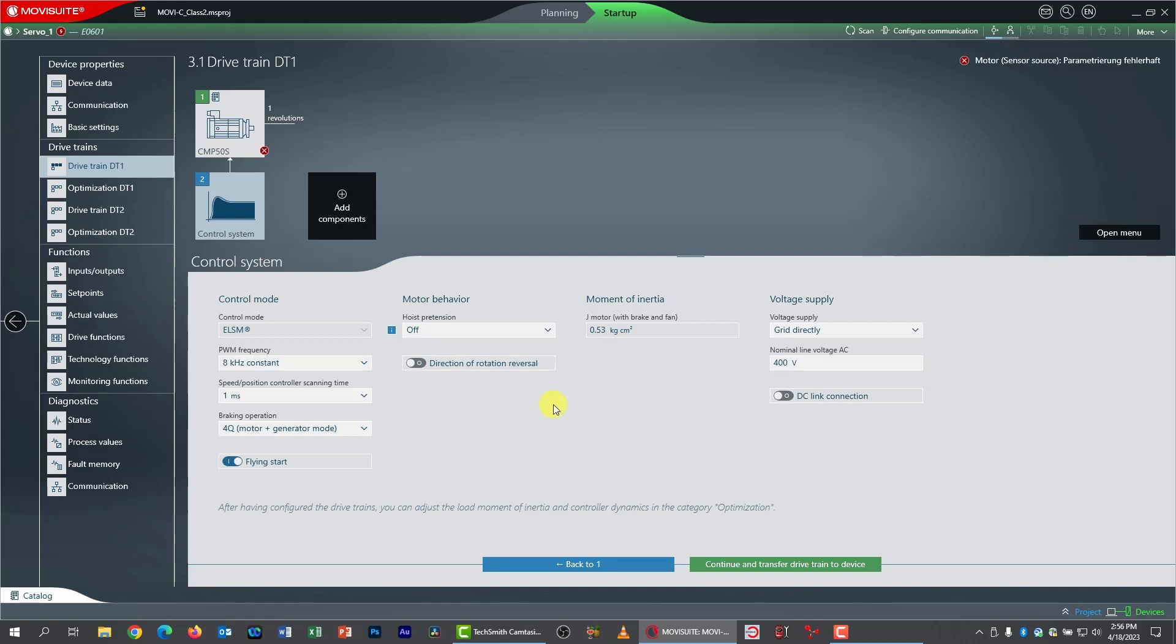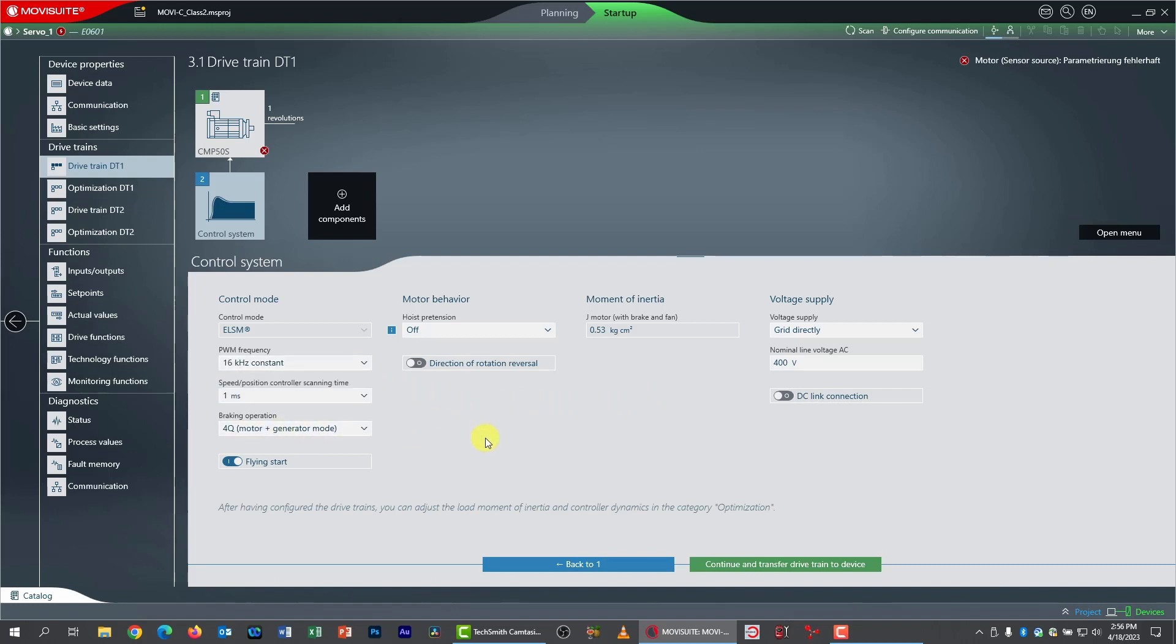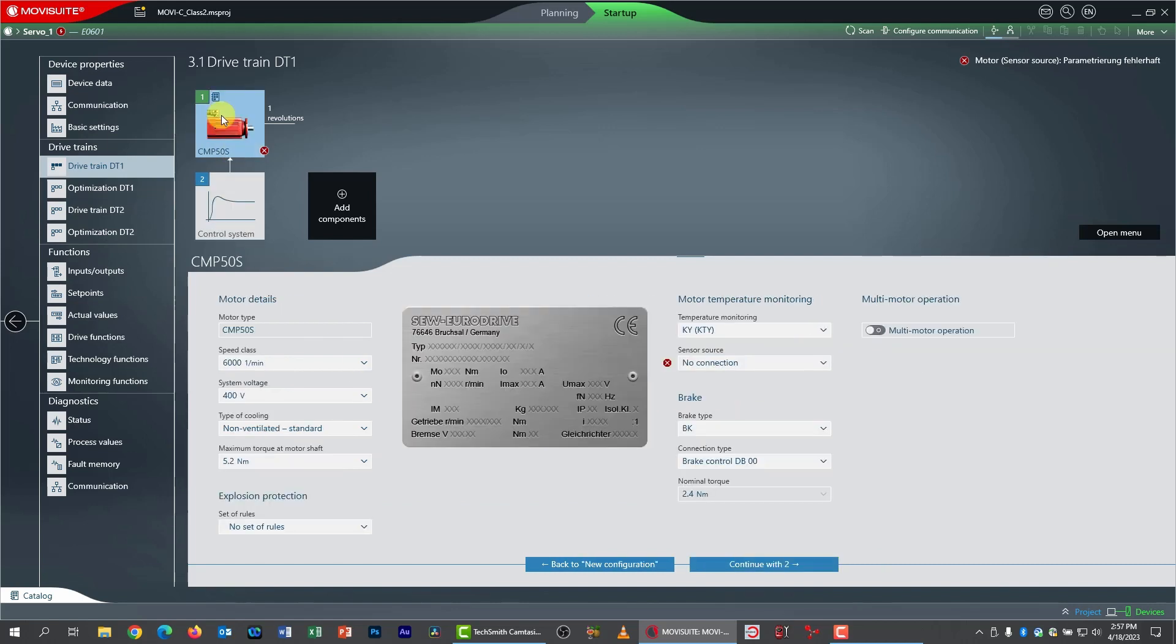MOVISUITE's intelligent enough to know that ELSM mode is my only possibility. That's okay. I'm going to go here to where it says pulse width modulation frequency and change it to 16, just so I don't have to hear the pulse width modulation. I'm going to go and key in my line voltage, which is 460.